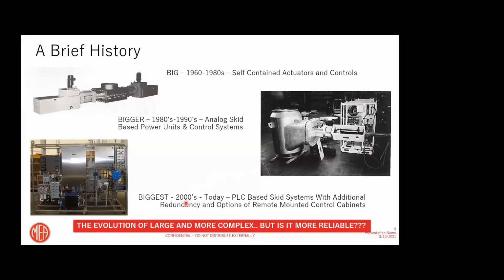And from 2000 up till today, these units got even bigger. Currently we have added numerous redundancies all around the place: position transducers, pumps, additional filtration systems. We added about 8 to 10 different transmitters to be able to monitor all sorts of pressures. And of course, it now comes with different types of PLC, single, redundant, triple redundant. So as we can see, these units progressed from bigger to even bigger over time.